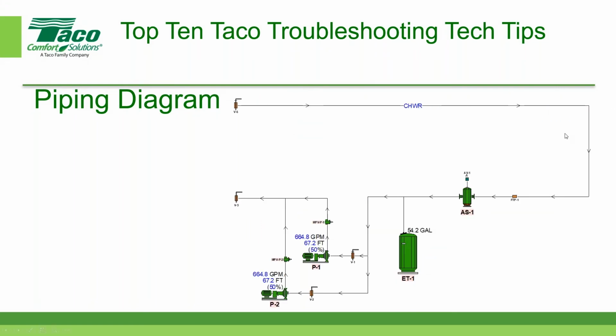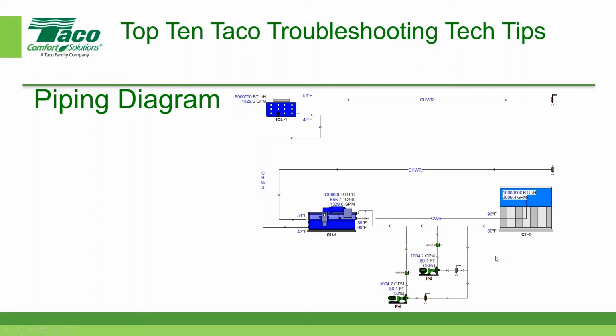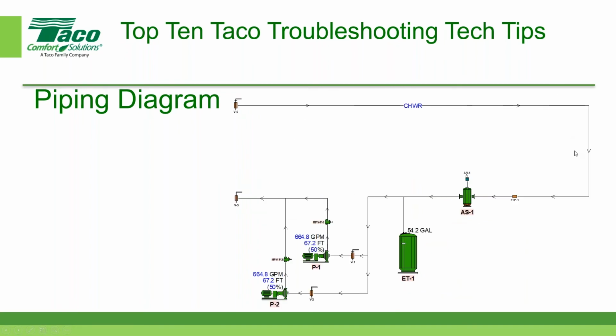Okay. And this is just the chilled water side of the diagram. The first diagram I showed you was the condenser water, and these two lines up here show the chilled water going out at 42, coming back at 54, and then the rest of the diagram, I split it up so it'd be easier to see. But they're not telling me they have any problems with the chilled water side, just the condenser water side. So I'm going to kind of ignore this half of the diagram.